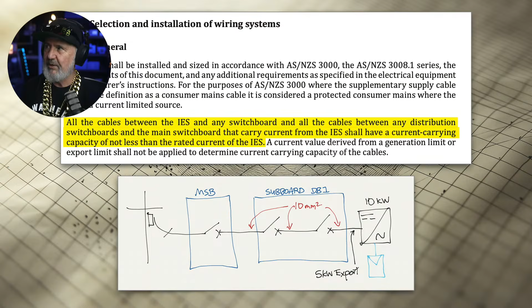Now, I also wanted to point out that when it comes to cable selection, you've got to be careful here. You might think that you've got a 5 kilowatt export limit and therefore using AS/NZS 3008, the standard for cable selection, you might think, oh, well, 5 kilowatts, that's only 21.7 amps. I could probably get away with a bit of 2.5 mil. But because this inverter can deliver 10 kilowatts, you've discovered that you actually have to go up to a 10 mil cable because you've got to consider derating as well on top of that. So that's for wiring enclosed in air, so in conduit. If it's in thermal insulation, it's even worse. So there you go. Just beware of underrating your cables.